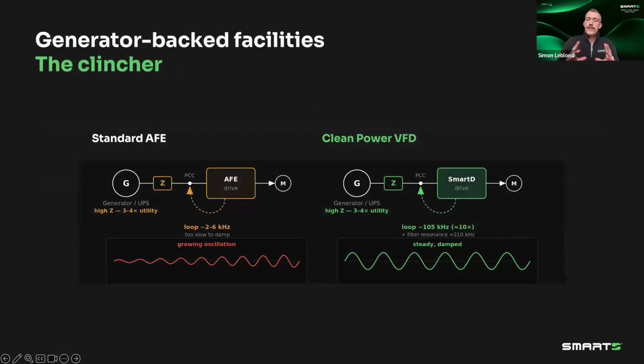And finally, this is where with data centers, you need to consider the generator and the UPS, which is a really weak source. Because it's a weak source, your active front end doesn't necessarily have the speed, the bandwidth in its control loop to hook on to that weaker source. So that really can lead to an interaction, grow into an oscillation, and either simple derating or instability and then nuisance trip. Because we are running a control loop at 105 kilohertz, you're really having much more bandwidth and you can maintain that stability in a much better way with these generators and UPS than with a standard active front end.